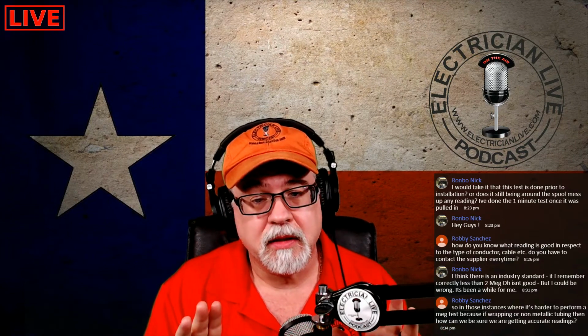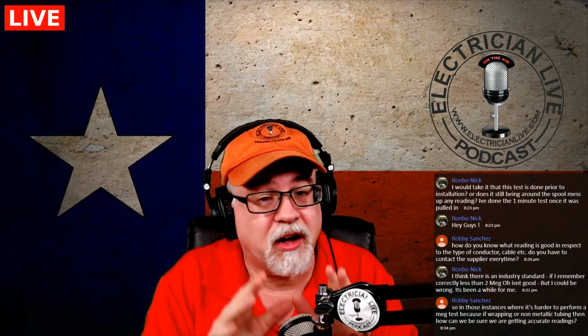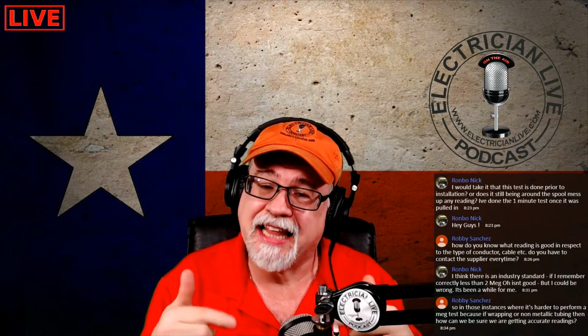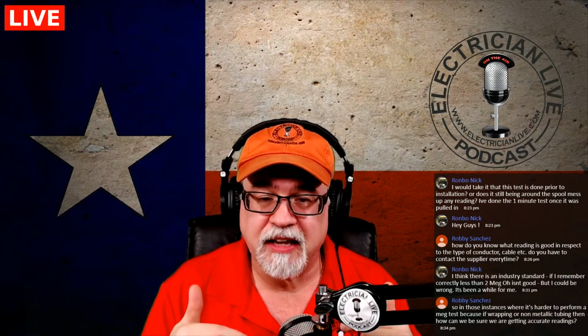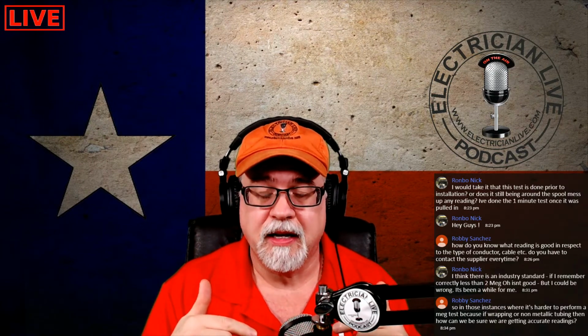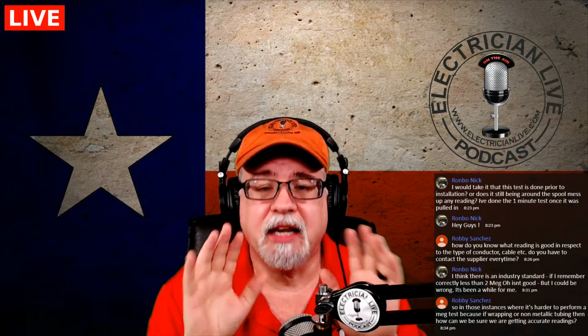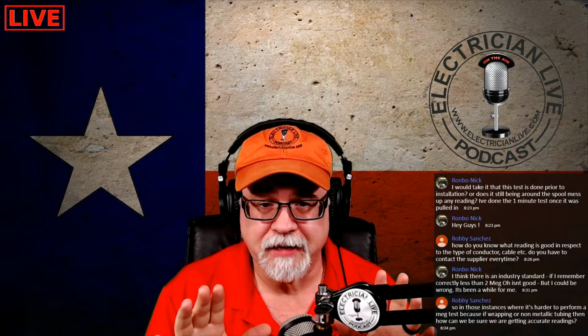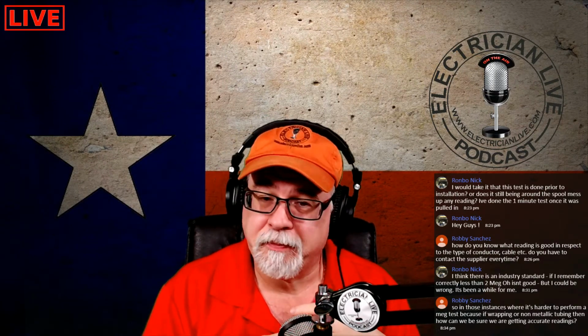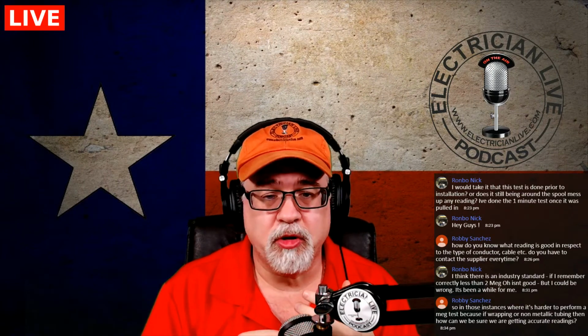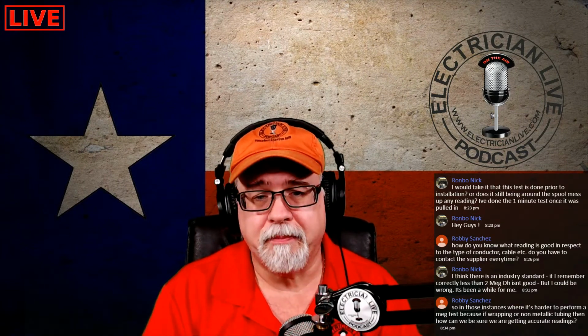Now I know that engineering standards, the engineers will put NETA standard 100 megaohms on there. But remember, in that NETA standard, it also says to consult the manufacturer because that's just a recommendation. Now let's talk about that standard, okay? Let's talk about it for a little bit. In that standard, that is typically designed for use with medium voltage type of products.